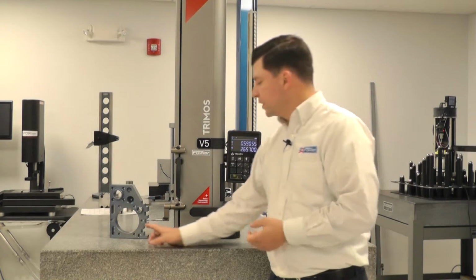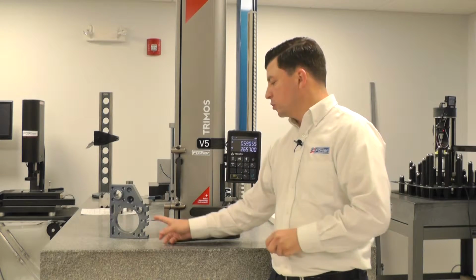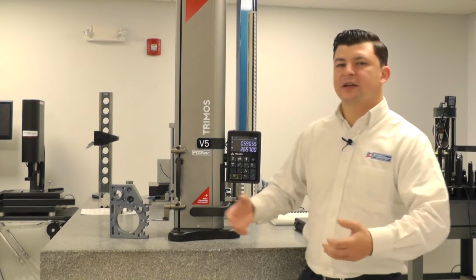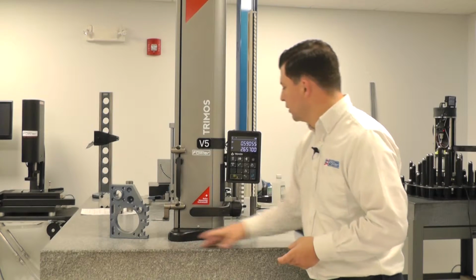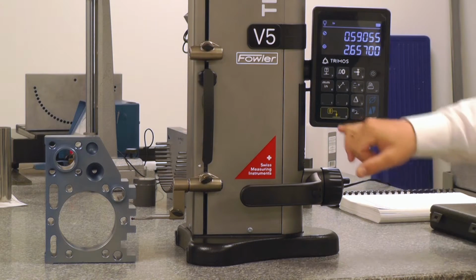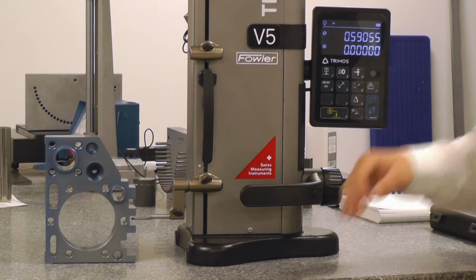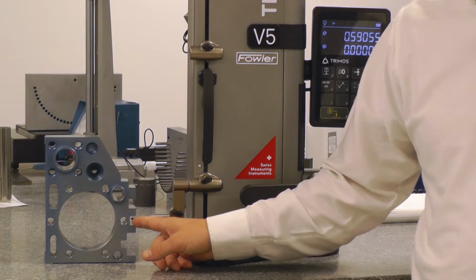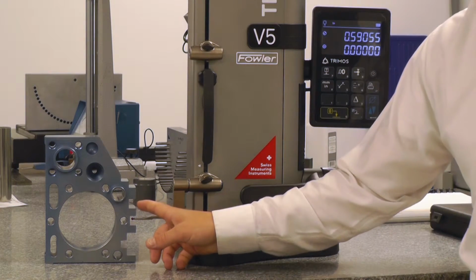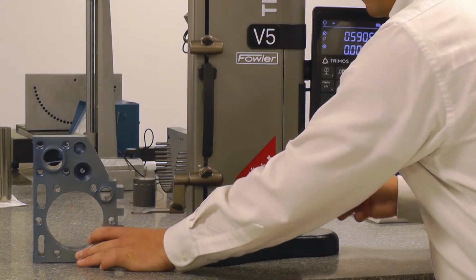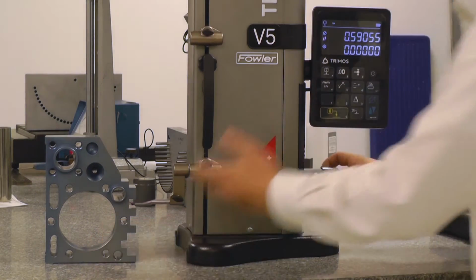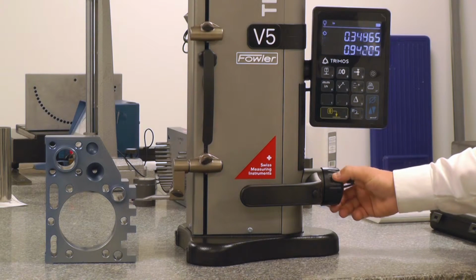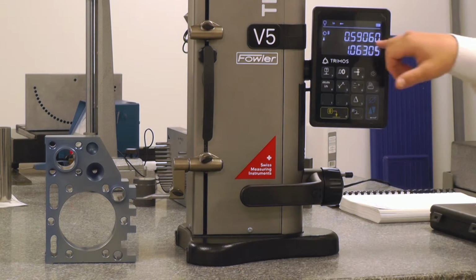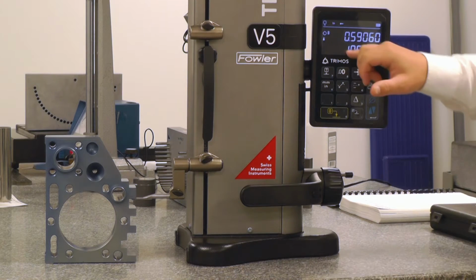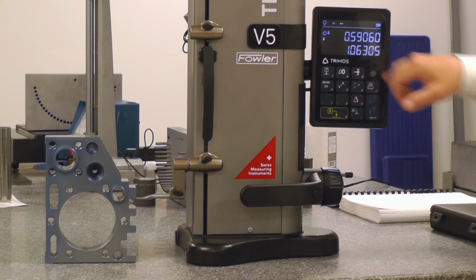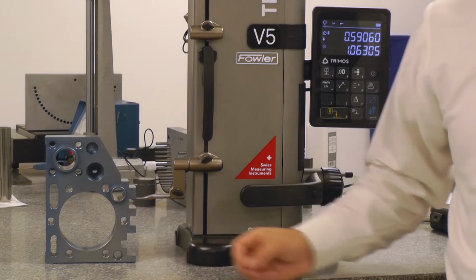Let's say we want to know center of the current slot we've just measured to center of the slot above it. Now we can establish a zero to the center line of this slot. Our value is here on the display, so if I hit the zero button, I've now established a zero position to the center line of this slot, and now I can measure the next slot. If I engage my probe down and up, again, 590 thousandths slot width, and now we have a little over 1 inch from center to center of these two slots.